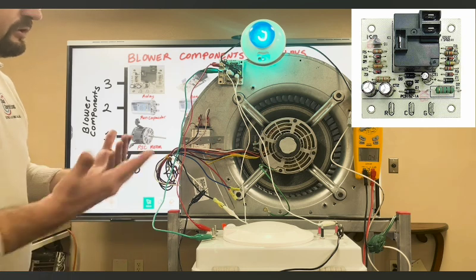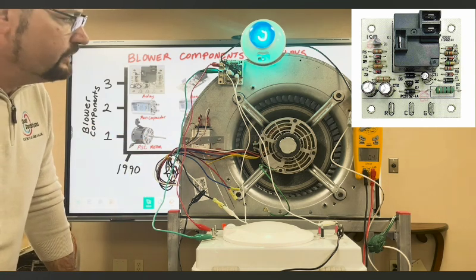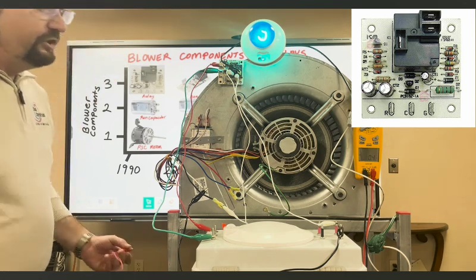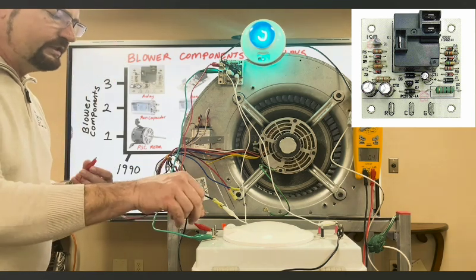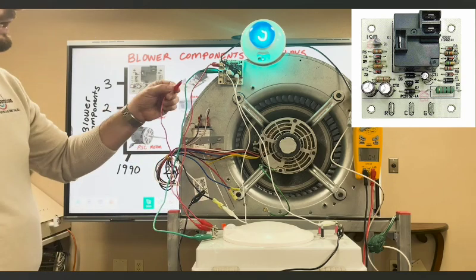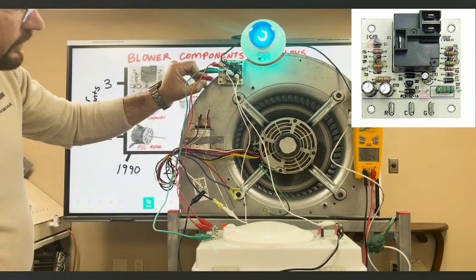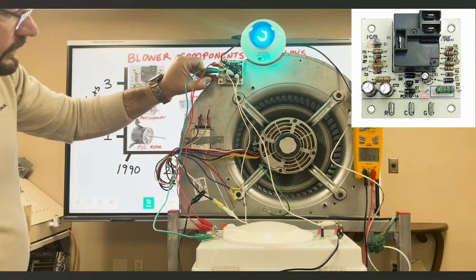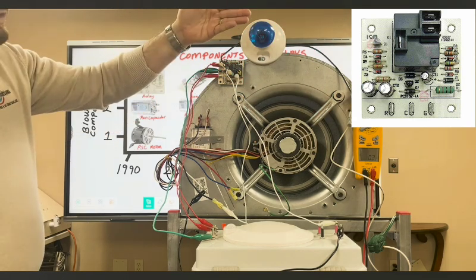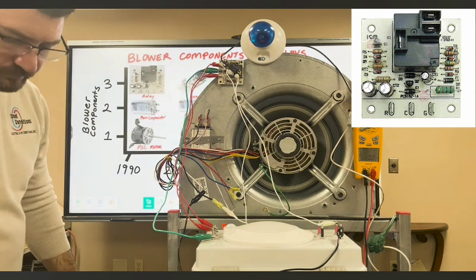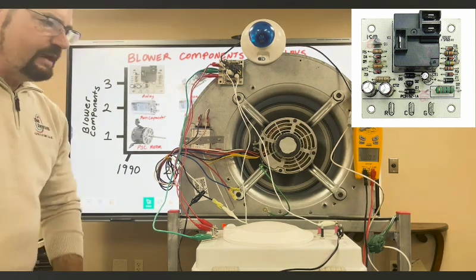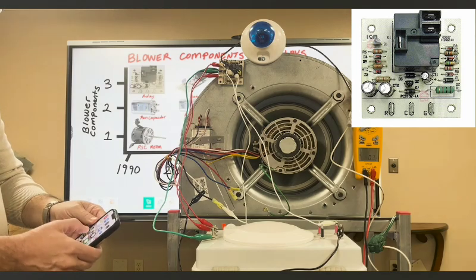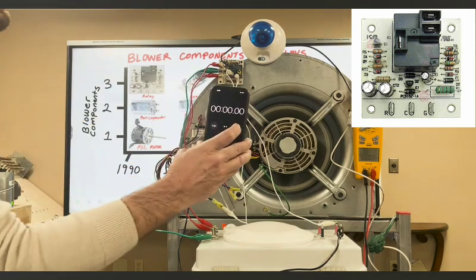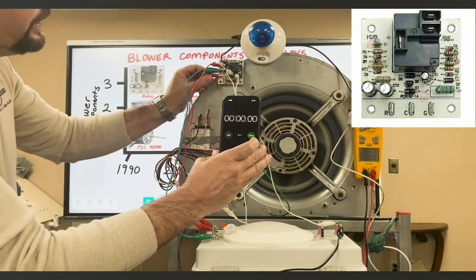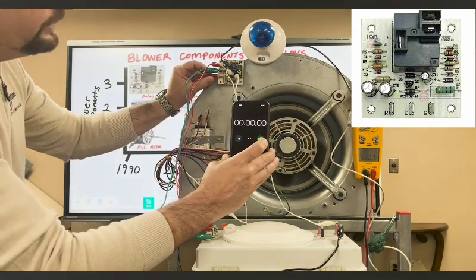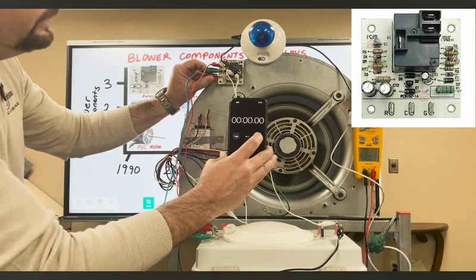Everybody learns a little bit differently, so we start playing with real power so we can understand our application a little bit better. All right, the only thing we're missing now is a G call. That G call is going to come from your thermostat. We're just going to give it 24 volts, and I don't have to keep it on there. However, I'm just going to leave it on there for a second and then remove it. And you see one load turns off and the motor is running now. I'm going to show you with my timer the moment we release that G call. The moment we release that G call, there's going to be a 50-second off delay, and then the light will come back on. And go.